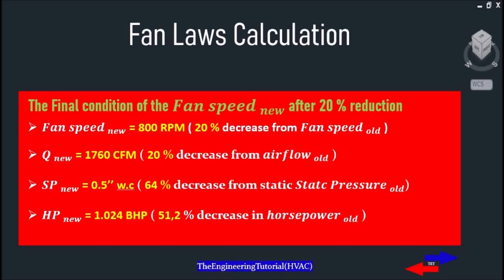The existing fan has a 2 horsepower motor. Based on the fan laws, we need to install a smaller fan motor requiring a horsepower of 1.024, capable of delivering 1760 CFM of air. That's it for today — thanks for watching this video.